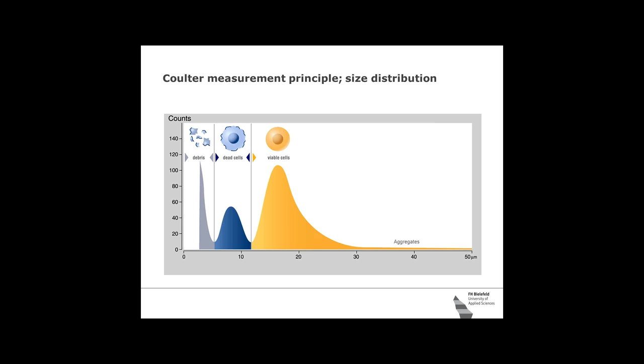But if you put cells into this instrument, the reality looks a little bit different. You get one very wide peak, which also shows you the diameter range your cells are in, and then you get a very tiny peak, sometimes only a shoulder attached to the main peak, and these are the raw data you get. So it's not an image like you look through a microscope. It is this diameter histogram, and you have to interpret it. The interpretation leads you to certain size intervals where you say, for example, in this case, 6 micrometers up to 14, 15 micrometers are the dead cells, and the viable cells are bigger than those. This way you can discriminate viable cells from dead cells.